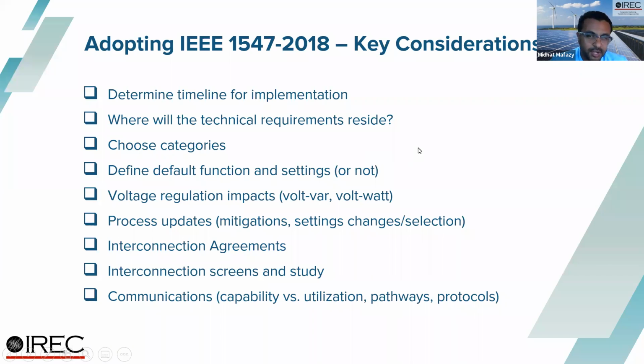Another key decision point is whether you will define default functions and settings, and whether you'll use the 1547 defaults or define your own. Same with voltage regulation impacts, volt-var and volt-watt. Are they activated or not? If activated, will you use 1547 defaults or your own specified defaults? With voltage regulation, you also have to be careful in that selection process.